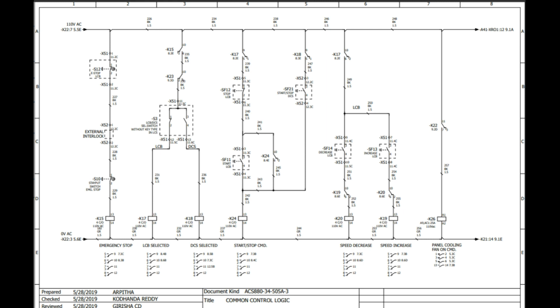If the drive has to run from local mode, then 110 volt will feed the K17 auxiliary contactor, that is LCB selected. If it has to run from DCS, we have to turn the selector switch to the right hand side, and K18 will get the supply, that is DCS selected. For example, we have to run the drive from LCB mode. K17 is selected and will come to the third tapping on the top. So K17 will get NC closed.